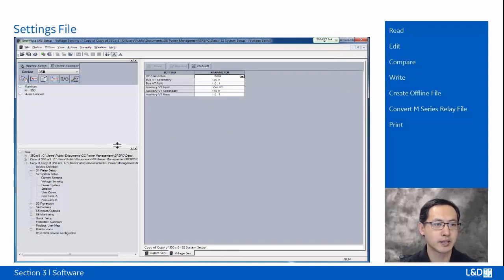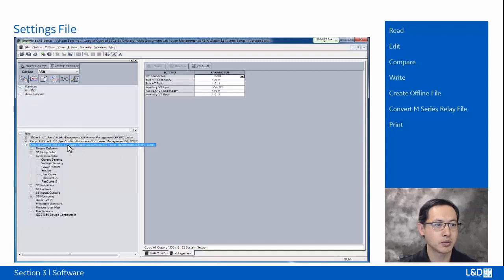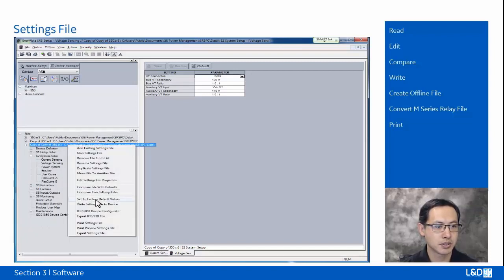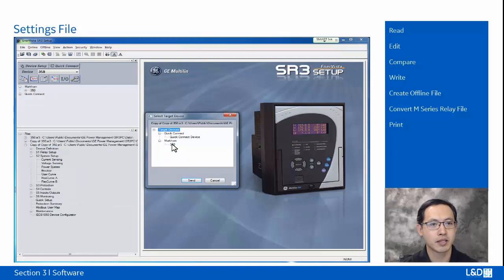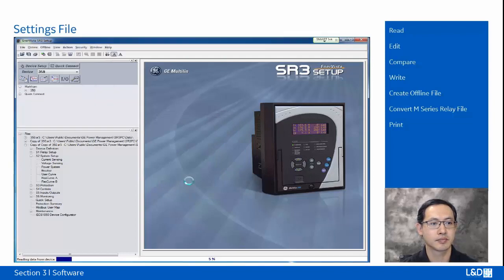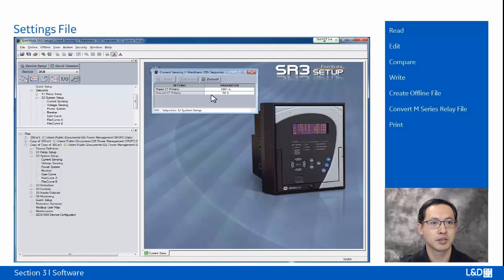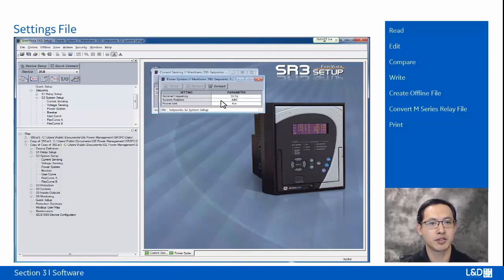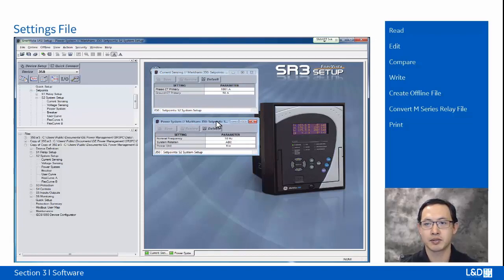In order to write a setting file back to the relay, we need to right-click the setting file and choose write setting file to device. So I'm writing this copy of copy back into the relay 350 and click send. And now this new setting file is uploaded back into the relay. So we can go to the relay online portion and open the set point just to check that new setting being uploaded. CT primary for the power system, 50 Hz. That's the setting file being updated.